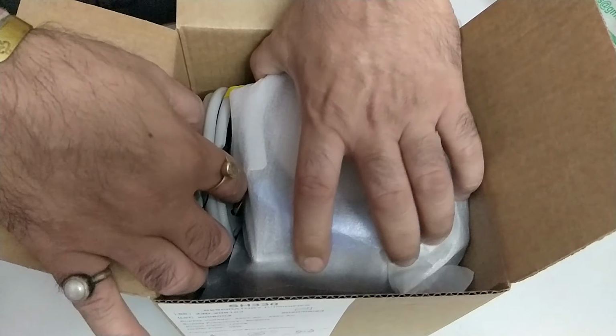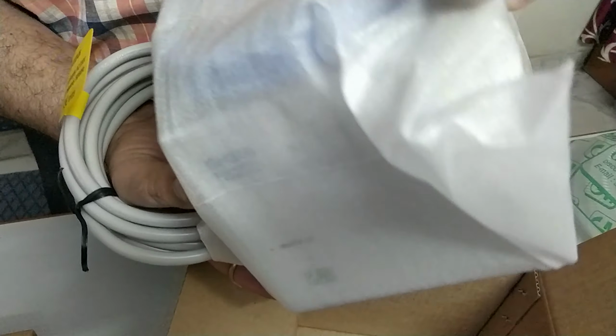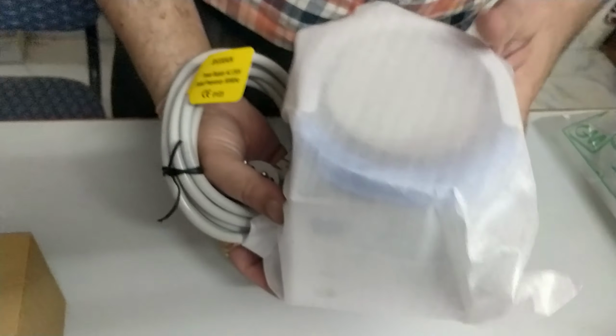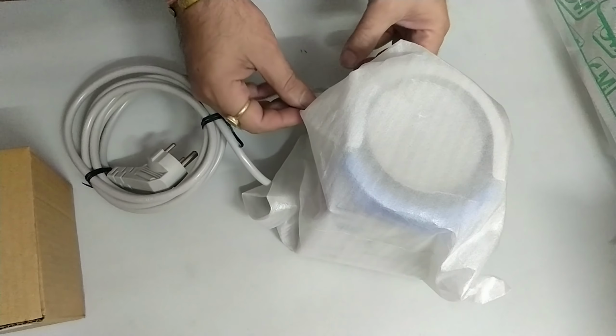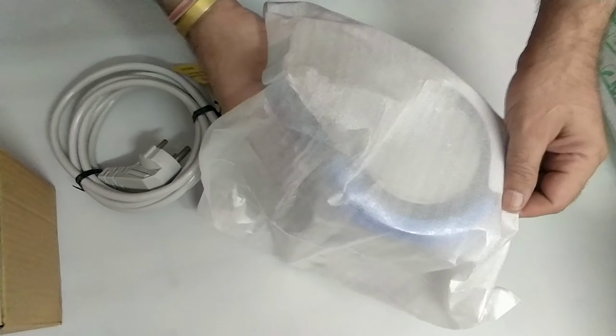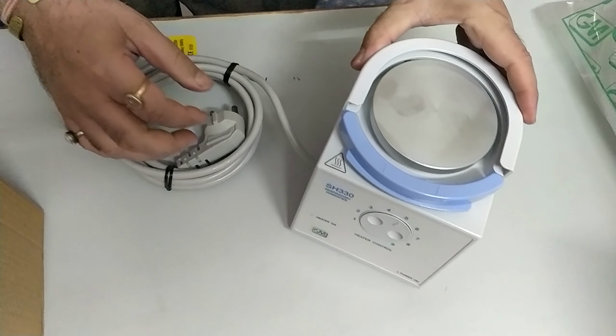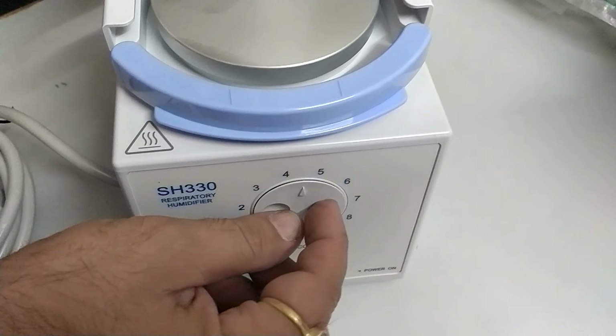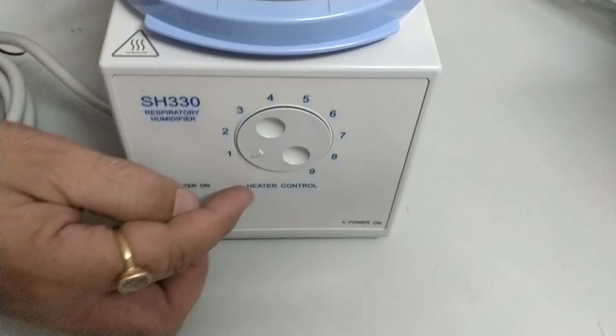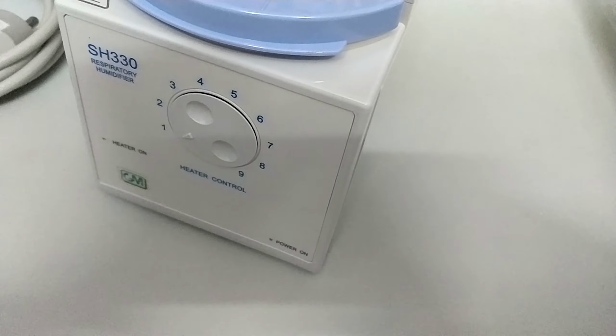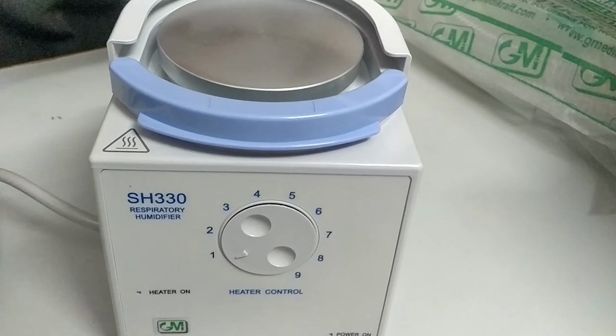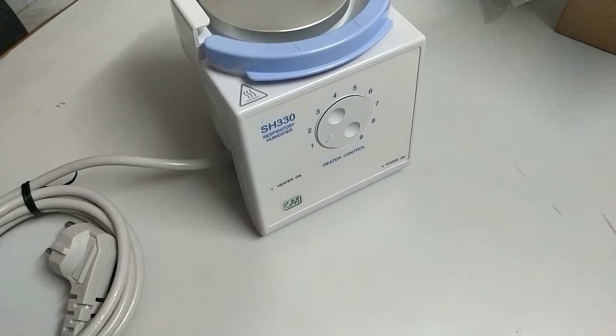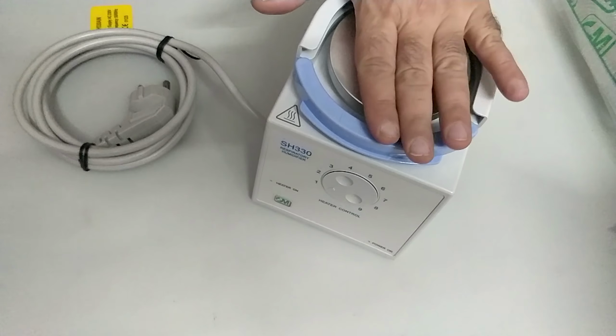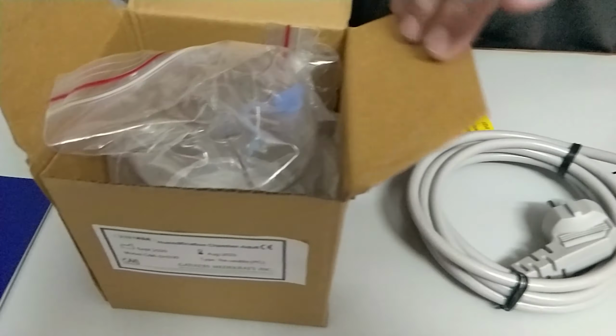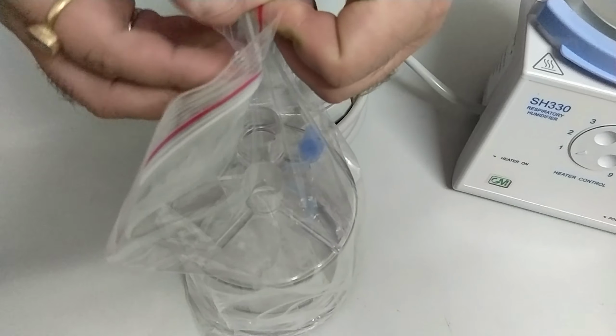This is the basic humidifier, which has manual control, for non-invasive adult and pediatric patients. This is the heater plate, and we have manual temperature control as per the heater control. We will show you a small demo of how to install it on the ventilator. You need a chamber, either an auto-feed or disposable chamber, or a reusable chamber. This is the reusable chamber, which can be autoclaved at 110 degrees.